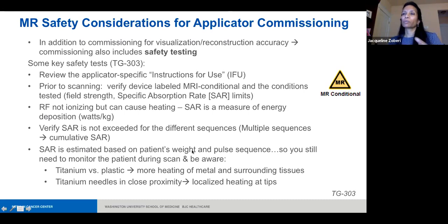The SAR reported on your MRI console is an estimate based on the patient's weight and the pulse sequence, so you still need to monitor your patient during the scan—check in and ask if they're feeling okay or any discomfort. Keep in mind titanium will lead to more heating, and titanium needles in close proximity create more localized heating at those tips, so if they're bunched up together you could really concentrate that heating.